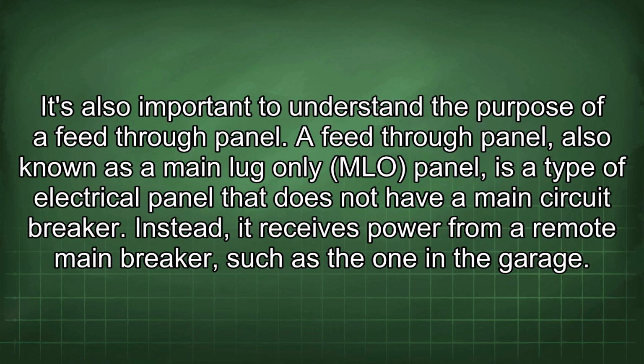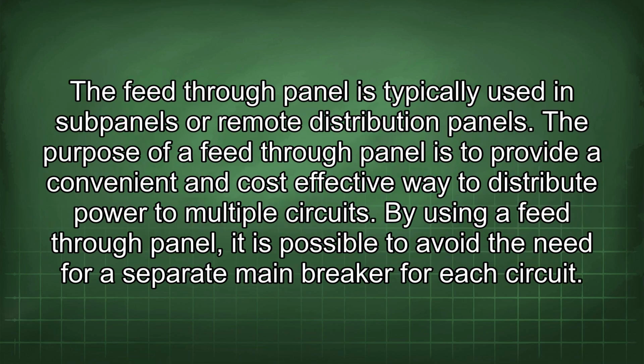It's also important to understand the purpose of a feed-through panel. A feed-through panel, also known as a main lug-only (MLO) panel, is a type of electrical panel that does not have a main circuit breaker. Instead, it receives power from a remote main breaker, such as the one in the garage. The feed-through panel is typically used in subpanels or remote distribution panels.